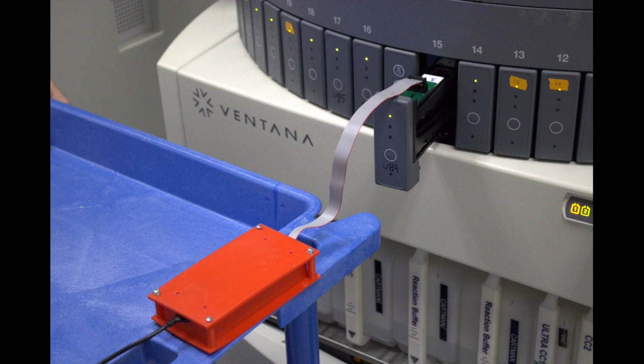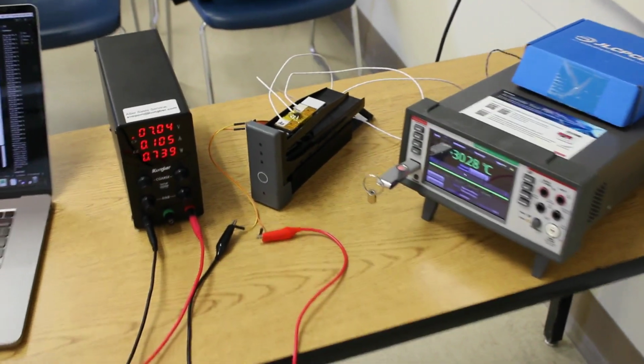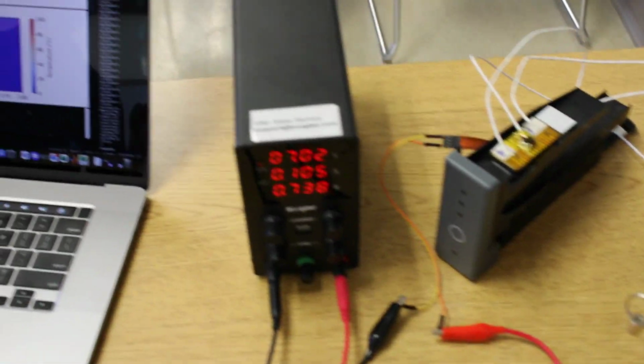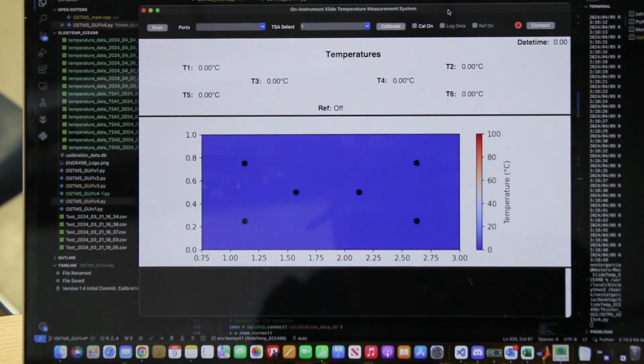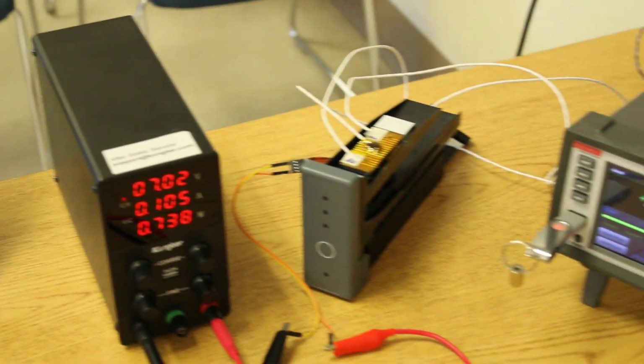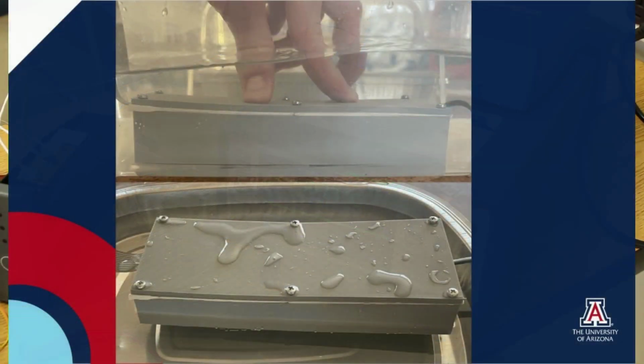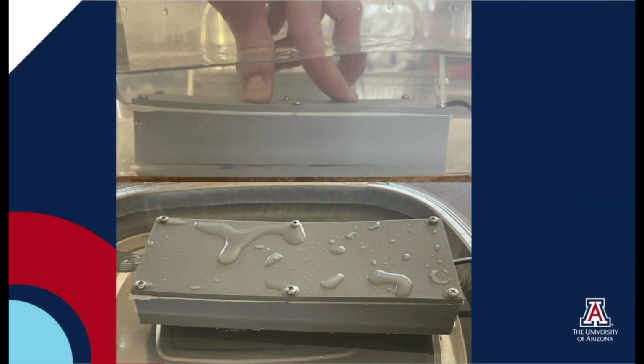The most important requirement of our project is that our device measures the temperature of the glass slide with an accuracy of at least 1 degree Celsius over a range of 40 to 100 degrees. This will be verified with tests with precise reference sensors. Finally, the casing around the sensor interface board was created to provide water resistance to any potential splashes that could occur, and this was tested by submerging the entire encasement in water without any leaking inside.